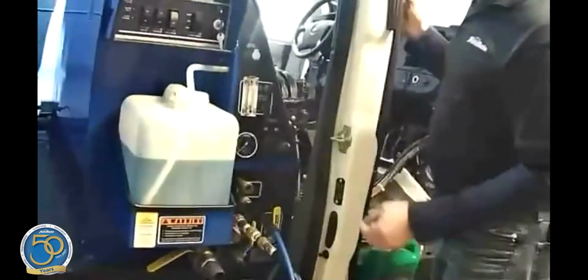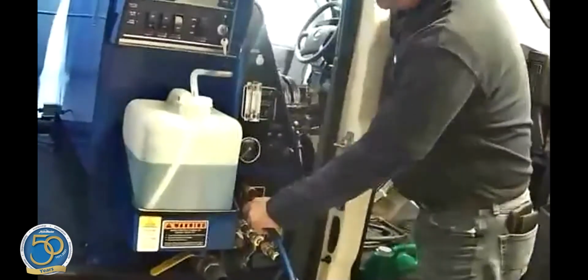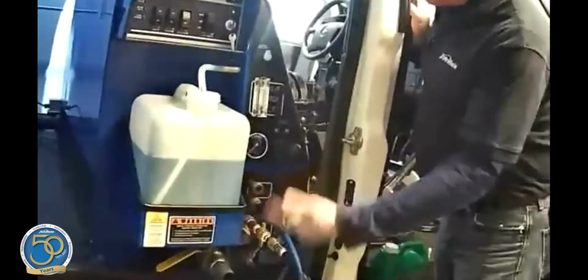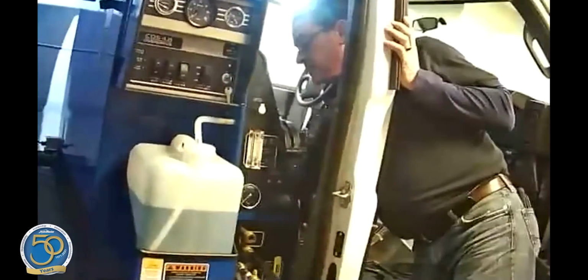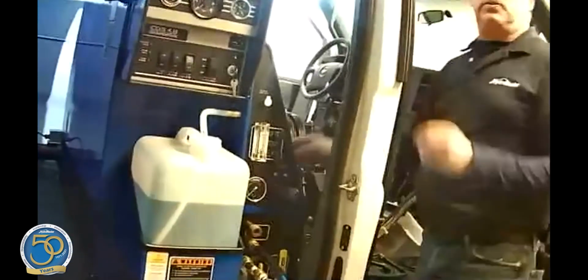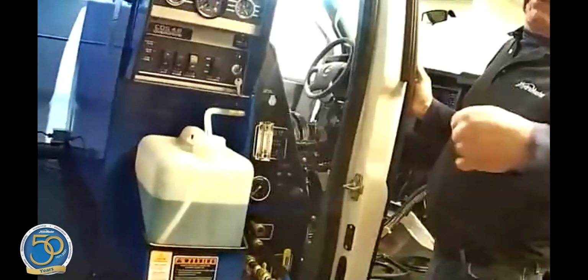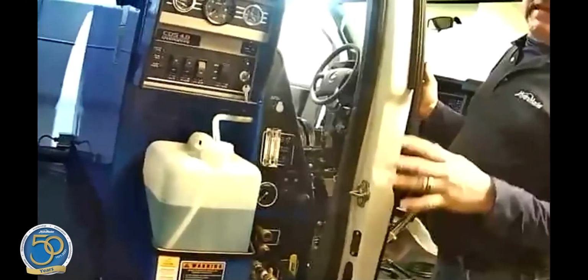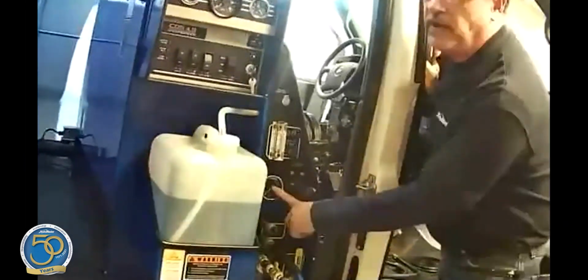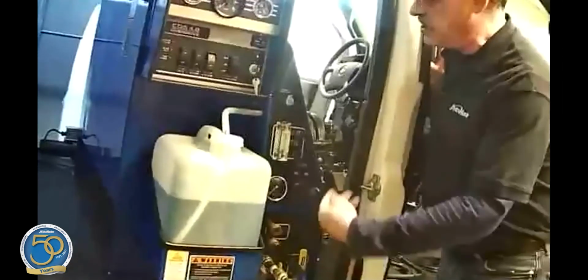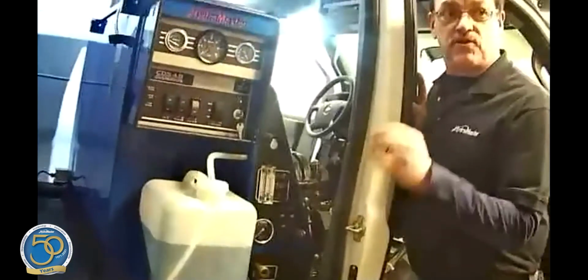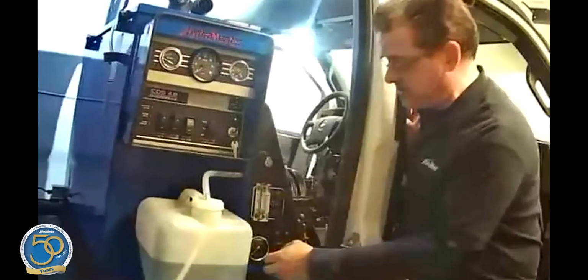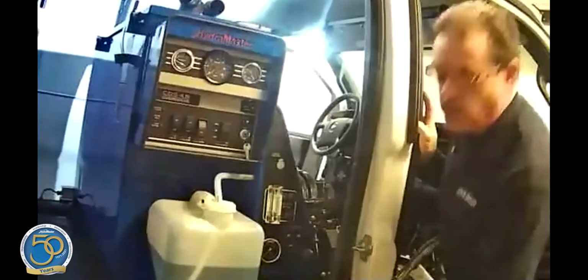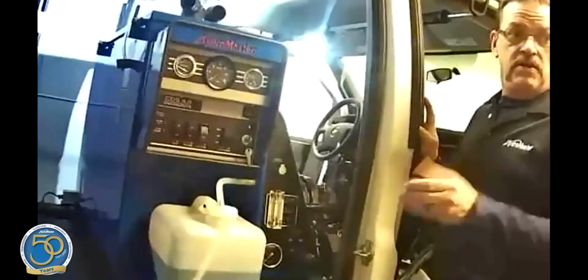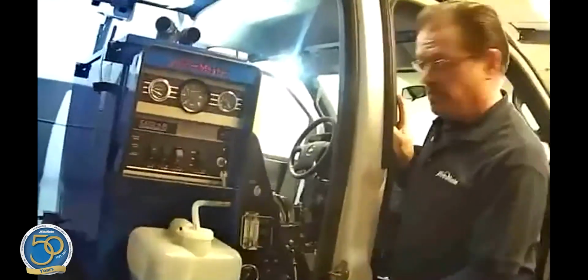Once you start recirculating the antifreeze through the system, take a small wrench and open the fitting at the back of the gauge where the hose attaches, until you get some antifreeze spitting out the back of it, then retighten it. That's a dead end hose, so antifreeze isn't going to flow through it unless you crack that fitting to allow some antifreeze up the hose and let it stay there. Then close it.